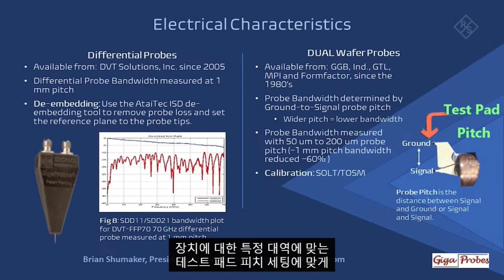The fundamental probe architecture of a dual wafer probe is two 50-ohm cables, and most manufacturers specify these probes as 50-ohm probes. However, they do not have electrical coupling between the two signal conductors and therefore are not true differential probes. The obvious key specification when selecting a probe to measure differential S parameters is getting a probe that can probe the same test pad pitches as the trace you need to probe. Now, the typical test pad pitch range for board probing is between 0.8 mm to 1.2 mm, or it could be a little smaller.